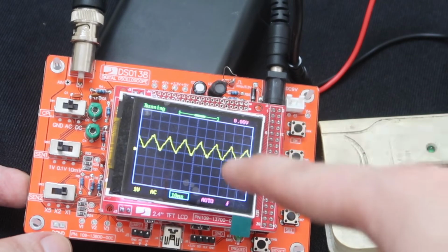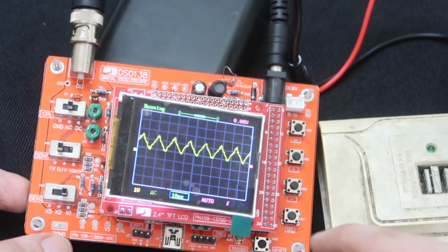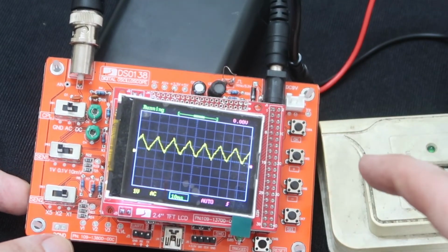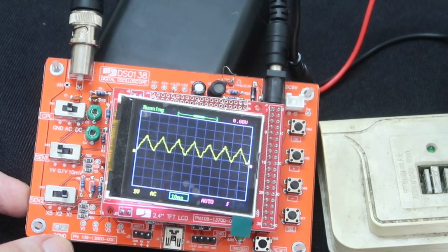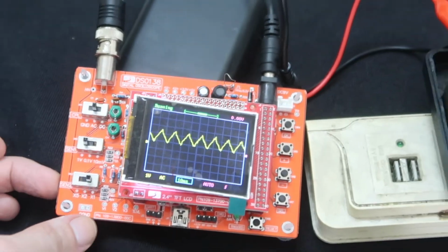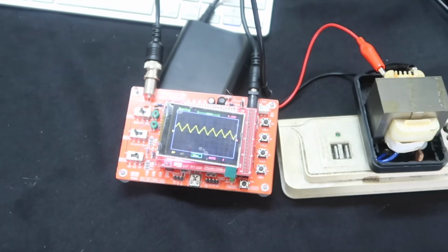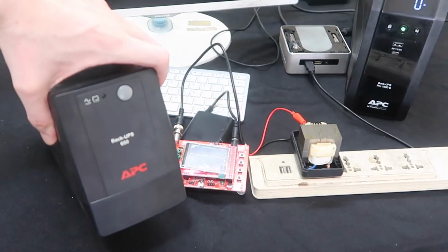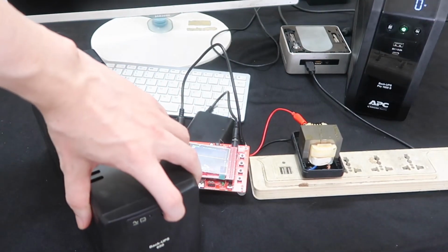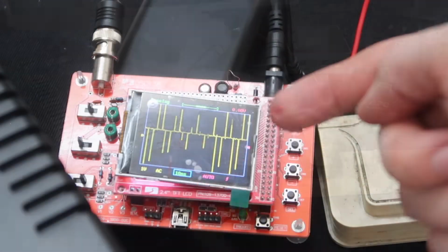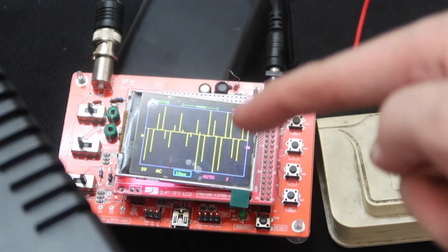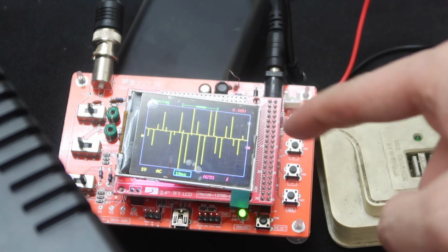It looks a little bit spiky, but I think that's simply because I haven't learned how to use this oscilloscope yet. But you can see it's pretty much a sine wave. Let me show you what the other UPS looks like, the modified sine wave. So this time we'll use our smaller UPS, which is a much more basic model. Immediately you can see that looks nothing like the pure sine wave. It's choppy, it's very choppy.